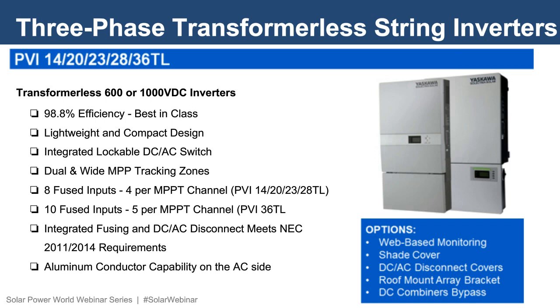The units have an integrated string combiner box with fused inputs. The 14 through 28 TL have 8 fused inputs, or 4 per MPPT channel, while the 36 actually accepts up to 10 fused inputs, or 5 per channel. All these machines have dual MPPT inputs, which give you the flexibility to design accordingly. Various string lengths, different module manufacturers, different array orientations, and different mismatch mechanisms can be accounted for. The integrated string fusing and the DC and AC disconnects meet the NEC requirements that Eric previously mentioned.